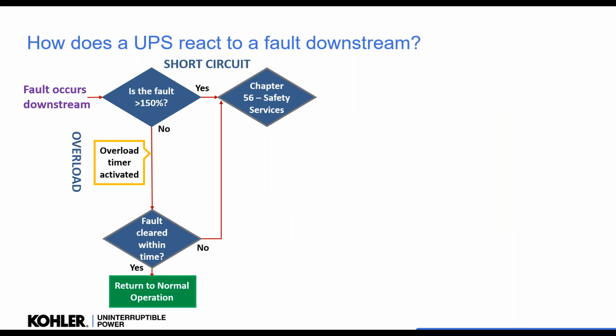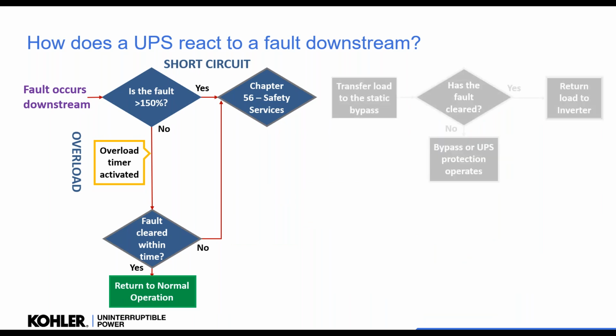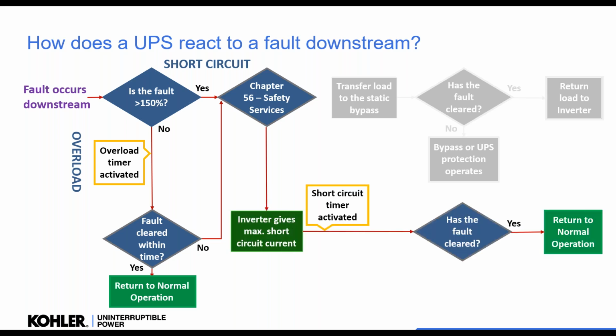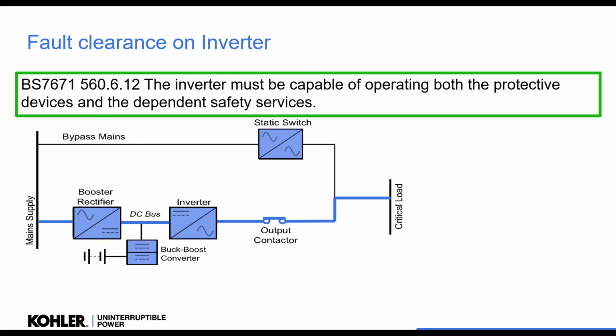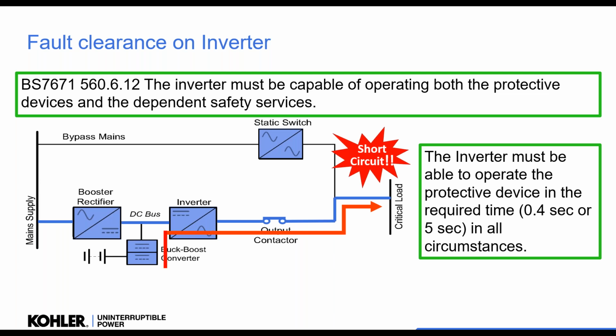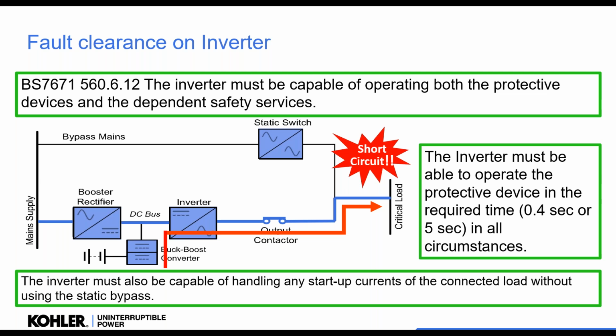Now, for a life safety system, we cannot rely on the mains being available. If we're in an emergency situation, 7671 says we must be able to do it off battery, so no mains. So we have to make sure that the inverter can trip the downstream fault and then return to normal operation to keep the remaining load running. Because if it doesn't, it's not compliant. So that means that if we have a short circuit on the output, the load must be fed from the battery, and the device must trip in a required time. Other parts of the regs say it must also be able to start up the connected loads without using the bypass.